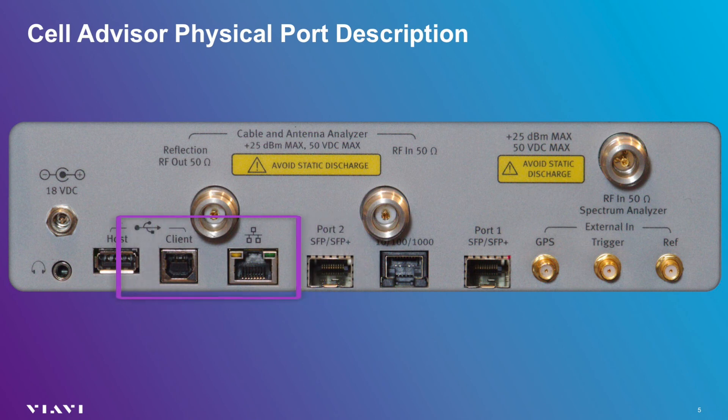The JD740 and JD780 Cell Advisors also have industry standard USB and Ethernet ports. The USB port may be used for a variety of devices, including flash memory sticks, a Wi-Fi adapter, or the P5000i fiber inspection scope. The USB client port is used to directly connect a PC; however, the network port just to the right of the USB client port is generally used for this purpose. When connected to one of these ports, a PC can be used to remotely control the unit, collect a measurement, or transfer files.